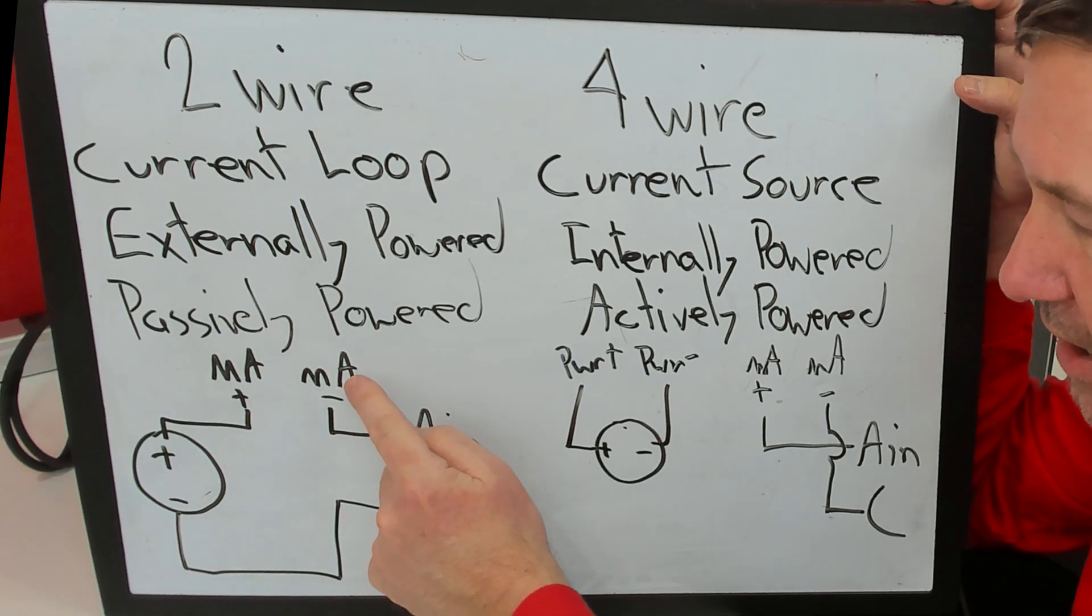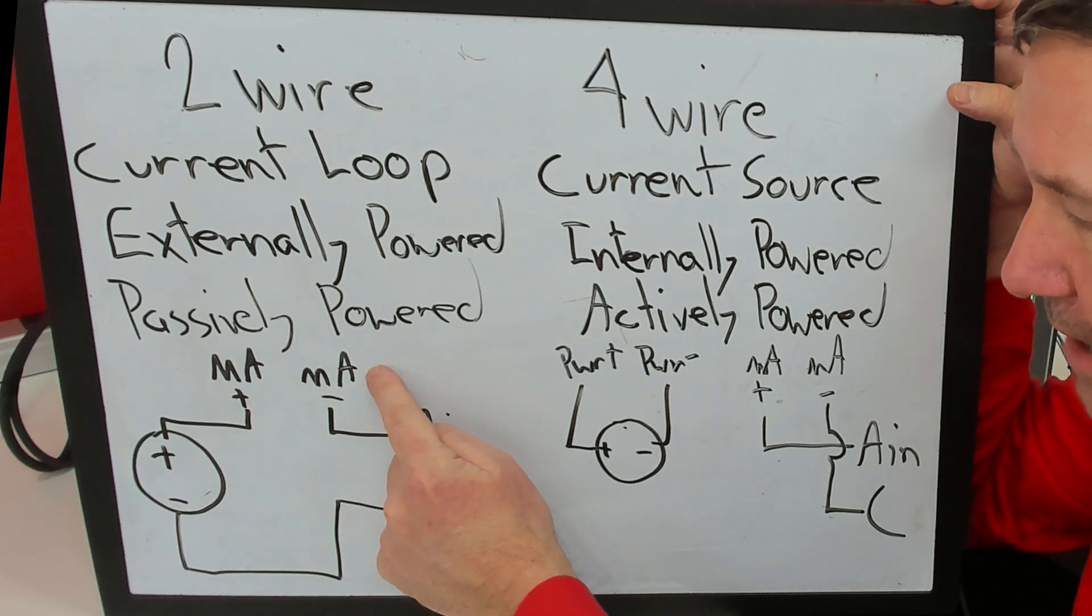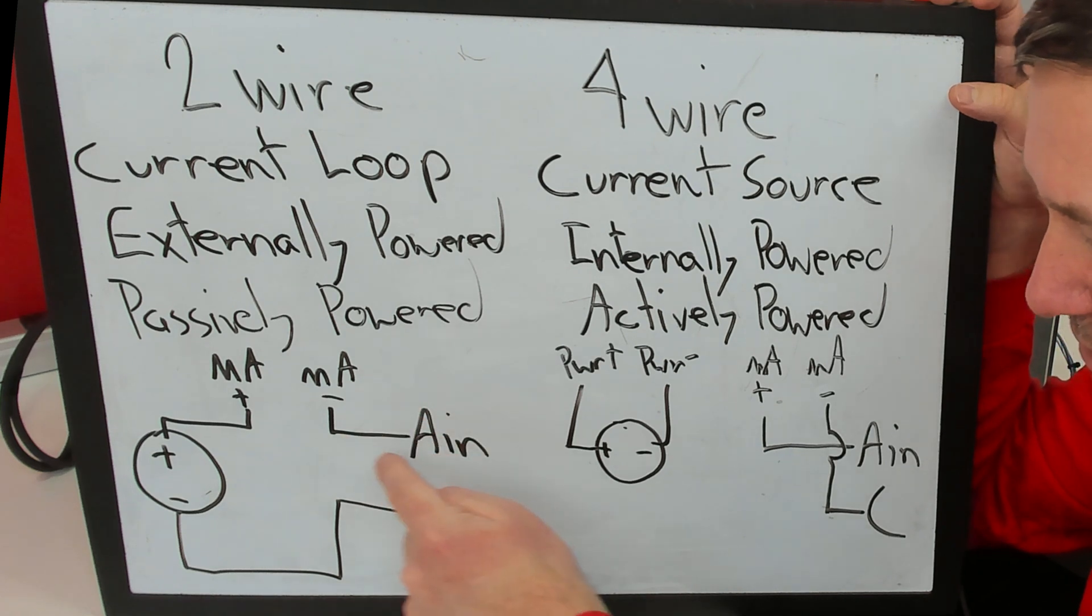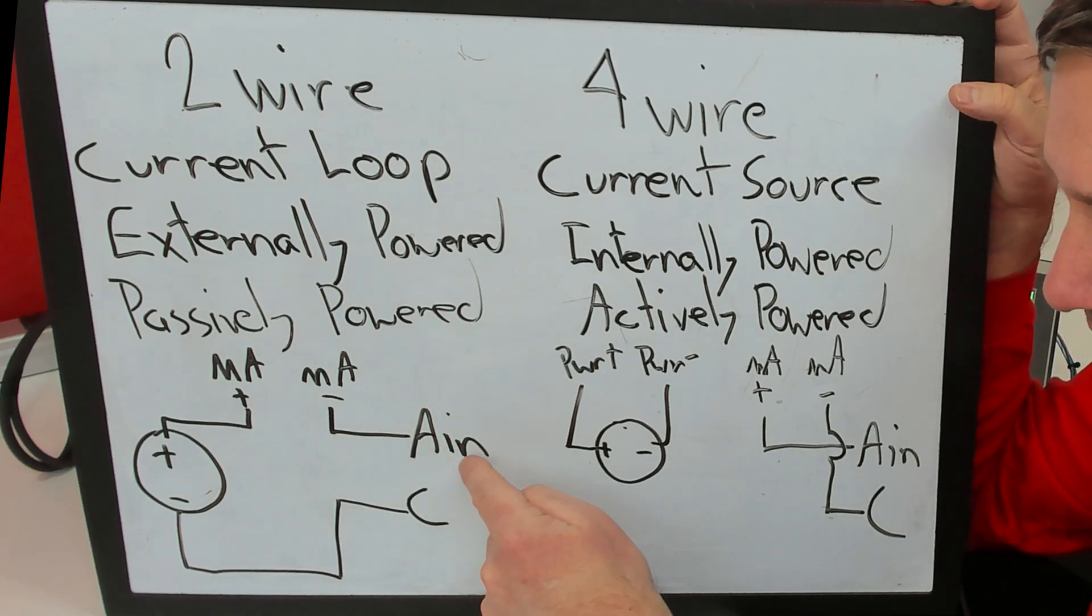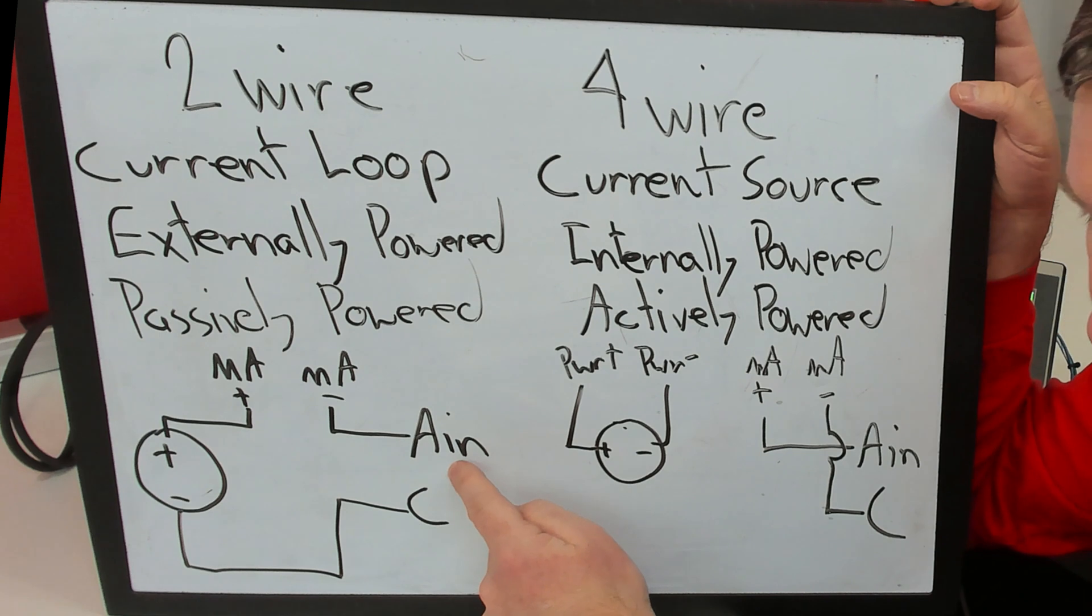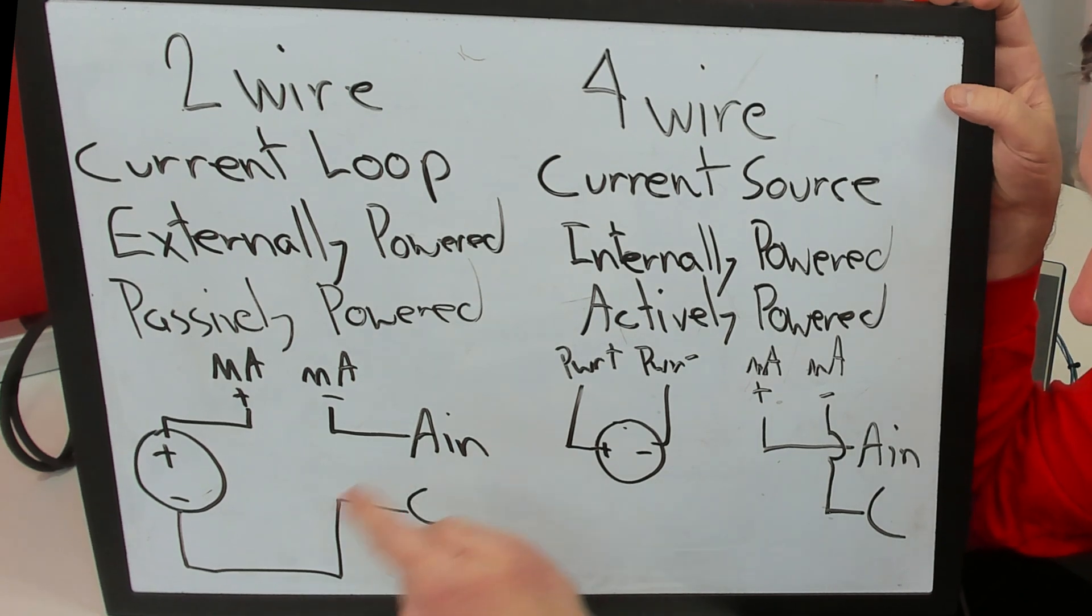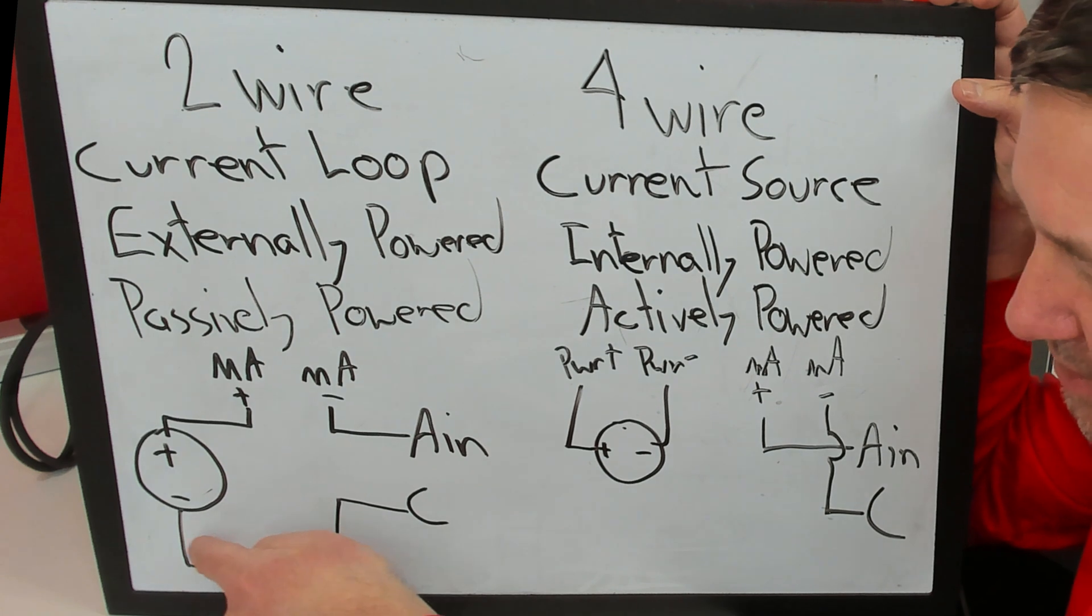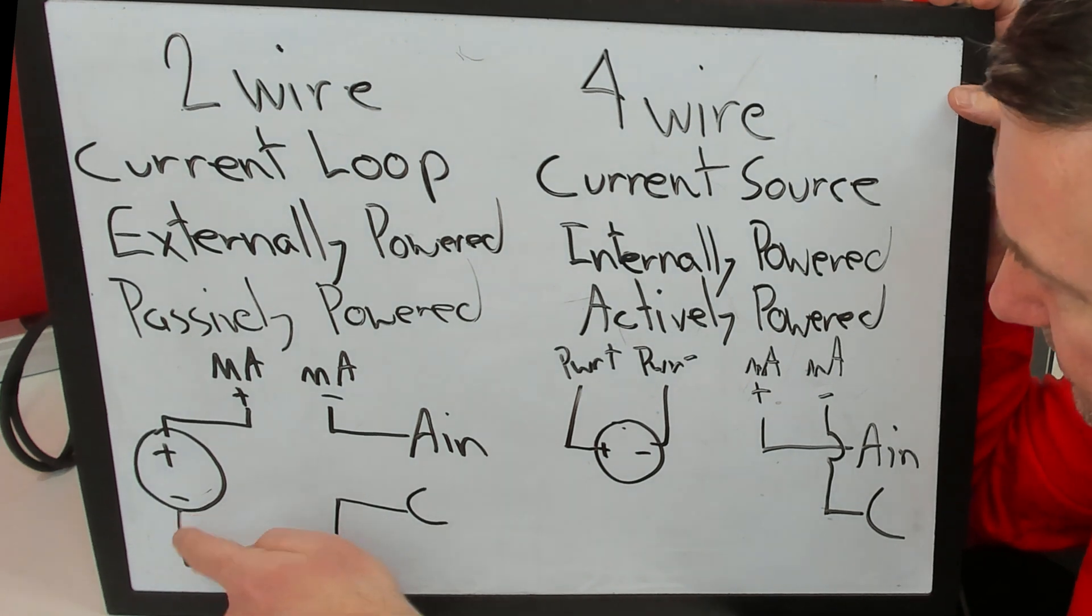We're going to come out of the milliamp minus of our sensor to our analog input, which will typically be our PLC input. Could be the plus on a meter also. And then we're going to take the common back around to the minus.